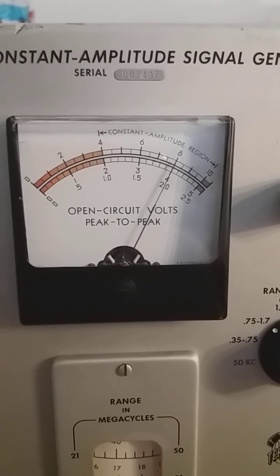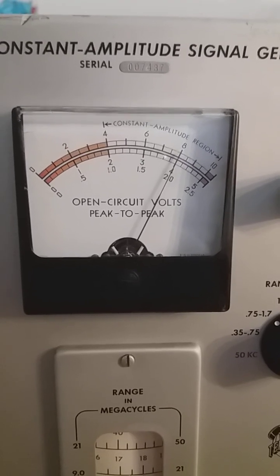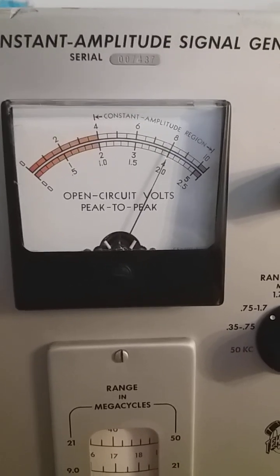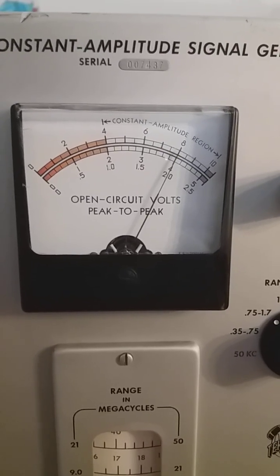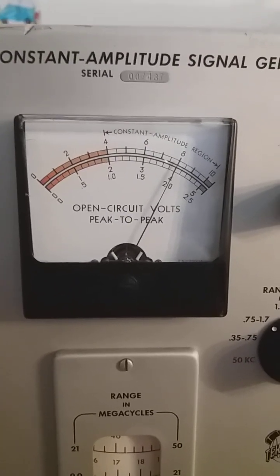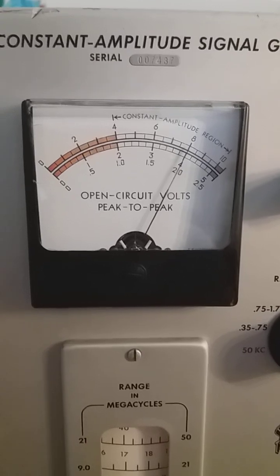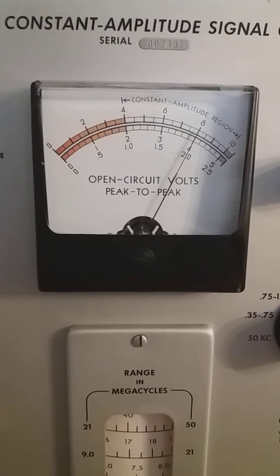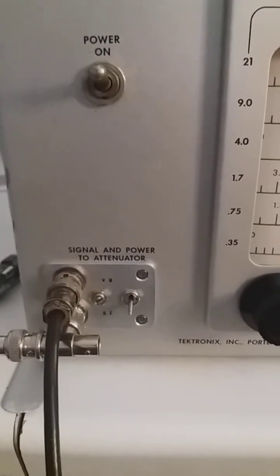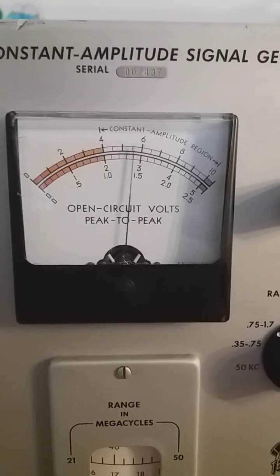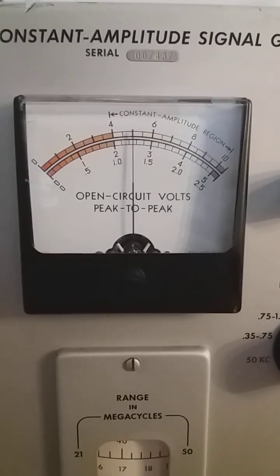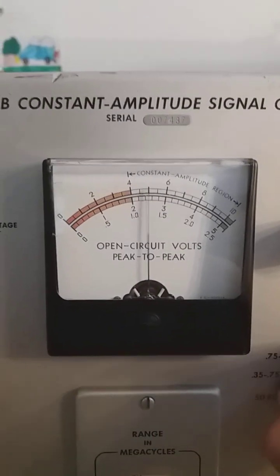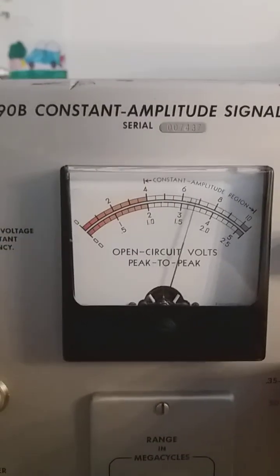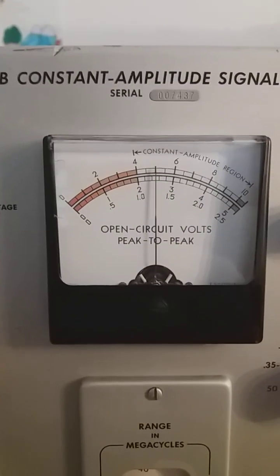So by using 2 external attenuators in the RF generator, I will have the ability to reach down to 0.1 volts and maybe 0.05 volts of output voltage, and still be able to correctly read the scales here in the meter without needing any change in these scales. Now let's test a bit the voltmeter. Let's put this to 5 volts peak to peak. Okay, we are in the RF position now, or generator position, and let's zero the meter. It's already zeroed, and we have put 5 volts peak to peak.